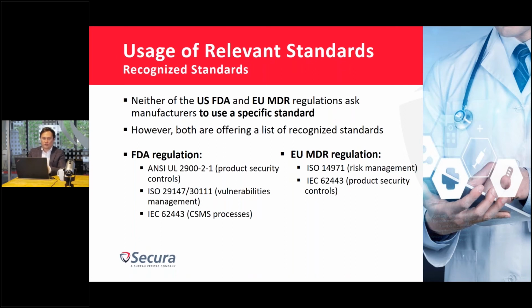The FDA regulation talks about UL 2900 as a relevant standard, but also other standards for vulnerability management and risk control, and also about IEC 62443 as a relevant standard, especially from a security development lifecycle and CSMS process perspective. On the other hand, the MDR again mentions IEC 62443, but more on product security controls, as well as ISO 14971 for risk management.